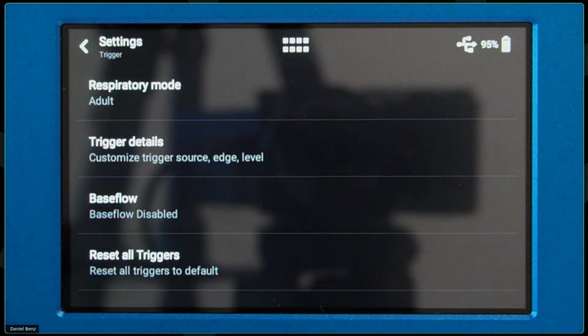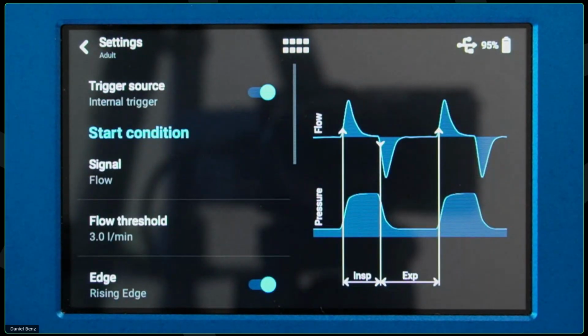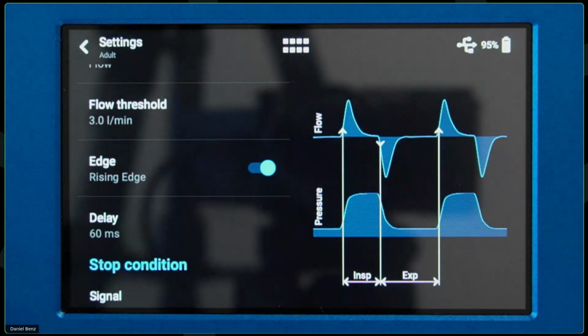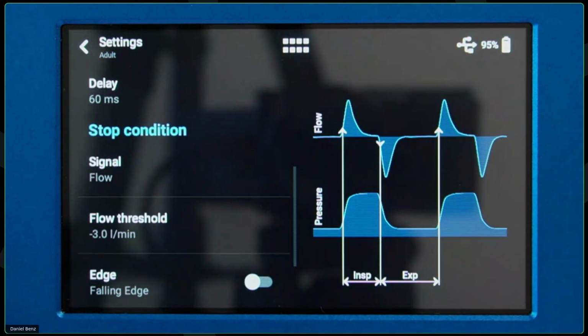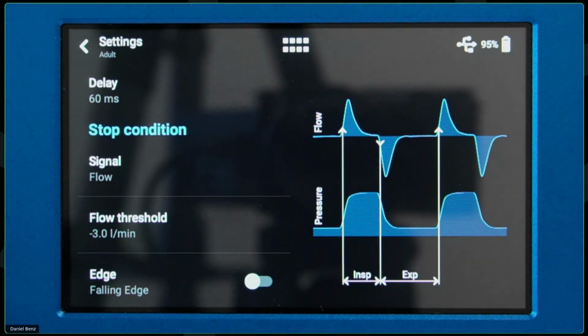Then let's go back and enter the trigger settings here. Trigger settings are needed for the device to be able to determine the breath phases. So the device needs to be able to determine whether an inspiration or exhalation is ongoing, and we do that through trigger settings. For my application here, I'm just going to leave them on my default trigger settings, which are on the flow signal with a start trigger on a rising edge at 3 liters per minute and a stop trigger on the flow trigger on a falling edge at -3 liters per minute.